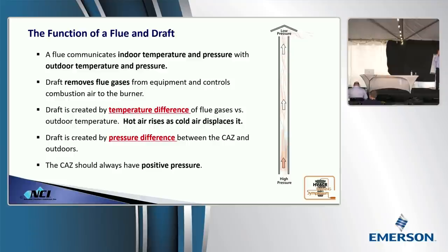As draft goes up, more combustion air. Draft goes down, less combustion air. So as draft is constantly moving up and down, our combustion air is changing. That's what the engineers in that ASHRAE study were measuring. As draft changed, they saw the combustion air rates that they were measuring through flow stations change, sometimes drastically. We want to start narrowing that down and fine-tune that range to something that's going to be acceptable. Now, of the two that control draft, temperature difference and pressure difference, which do you think has more of an effect, temperature or pressure?